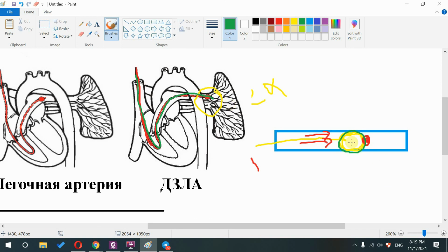When it's there, what do we do? We inflate a balloon. When this balloon is inflated, we basically block the walls, so the blood from behind it cannot pass. So the blood from the pulmonary artery cannot pass forward. If it cannot pass forward, it will not affect the sensor. The sensor will be only affected by pressure coming from the front.